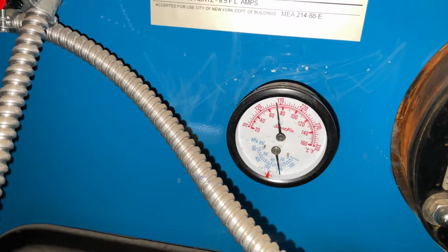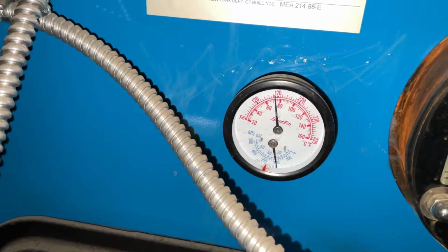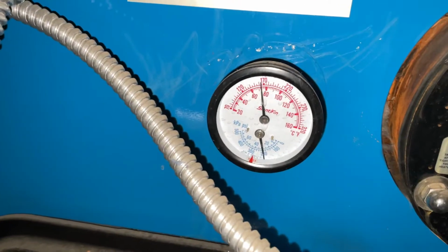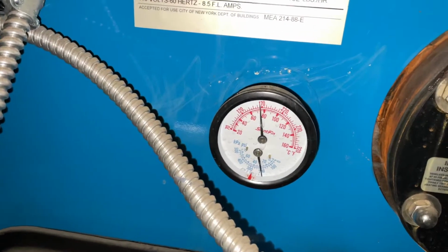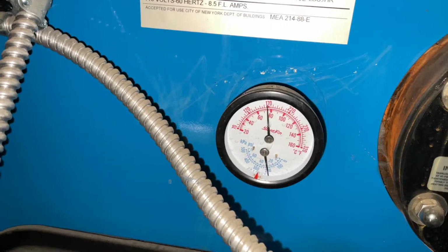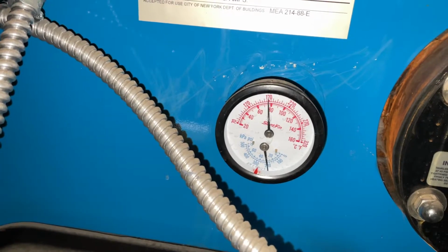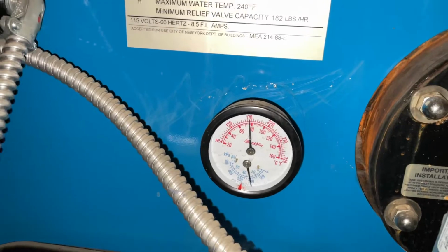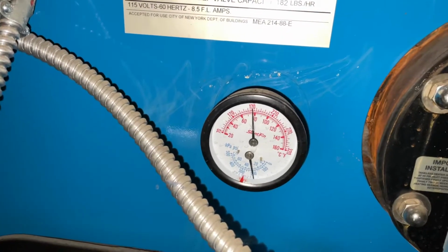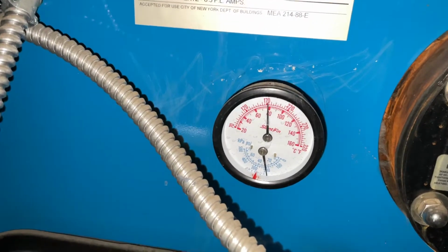Well, I don't know. I am getting heat in the house, everything's working, but I do notice for the upstairs zone, it runs for quite a while, while downstairs, it runs no more than 3 to 4 minutes. You can have the thermostat set to 90, for example, and when this thing fires up, it'll be a 3 to 4 minute run. The circulator pump, of course, will keep running until the thermostat's satisfied. But upstairs, on the other hand, it literally runs for like 15, 16 minutes straight.